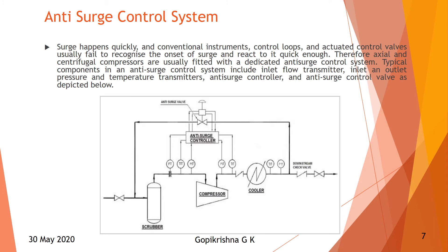The anti-surge control system: surge happens quickly and conventional control loops and actuated control valves usually fail to recognize the onset of surge and react quickly enough. So axial and centrifugal compressors are usually fitted with a dedicated anti-surge control system. Typical components include: an inlet flow meter, flow transmitter, inlet and outlet pressure and temperature transmitters of the compressor, an anti-surge controller, and a high-speed anti-surge control valve.